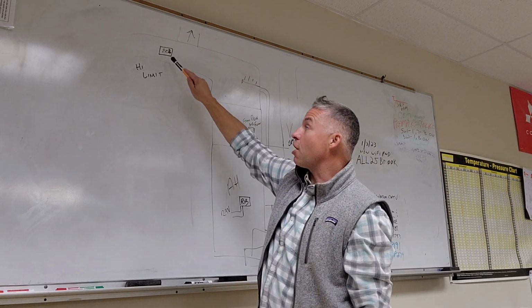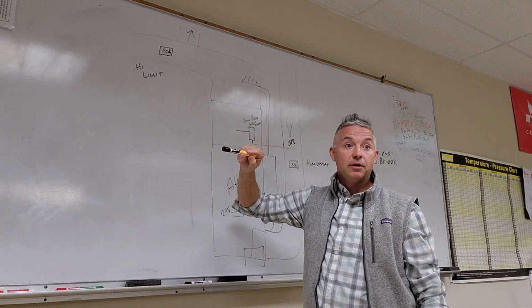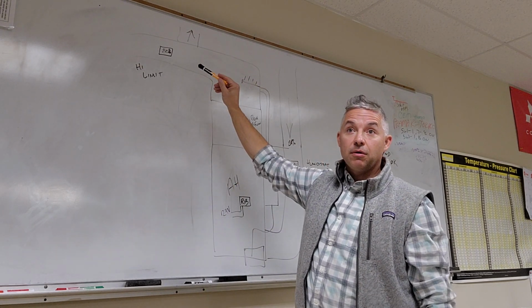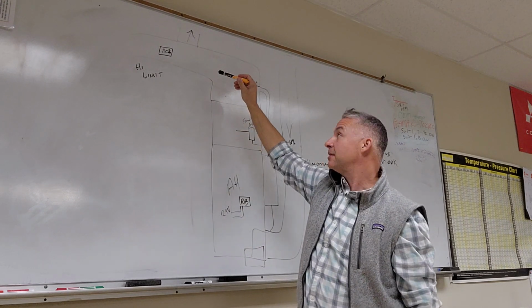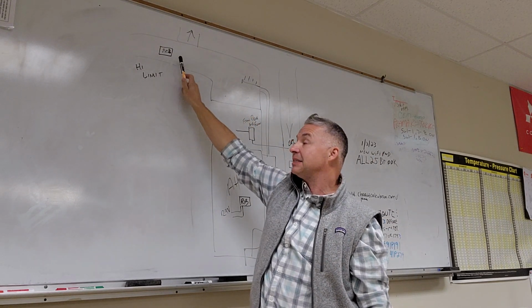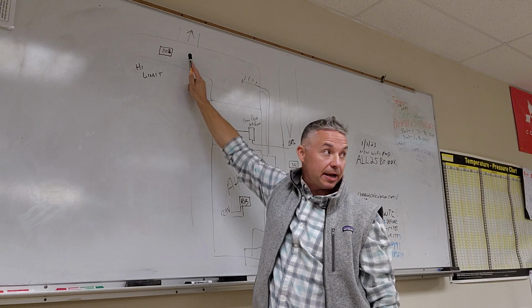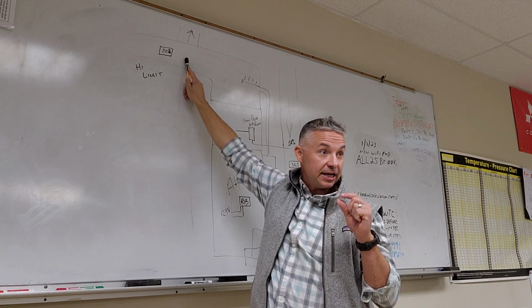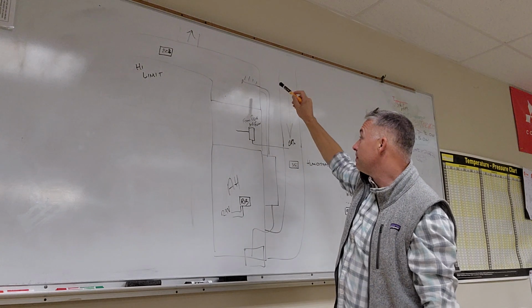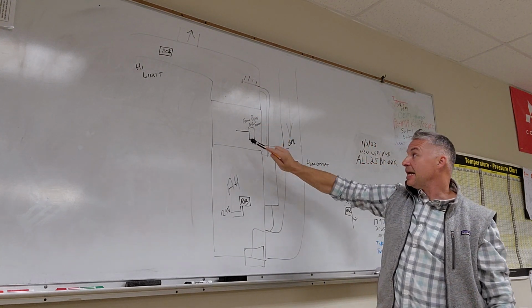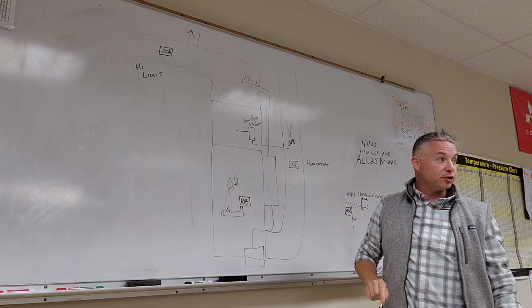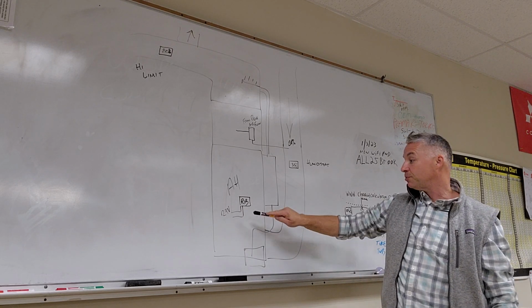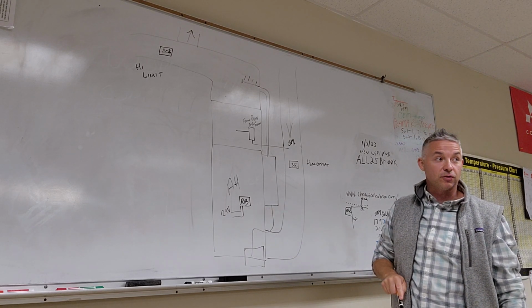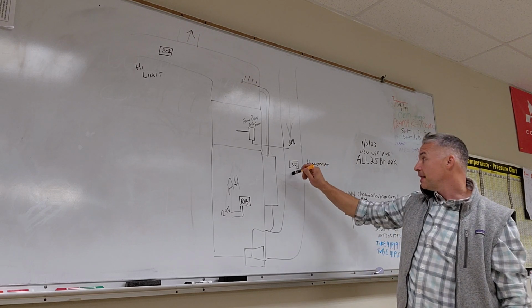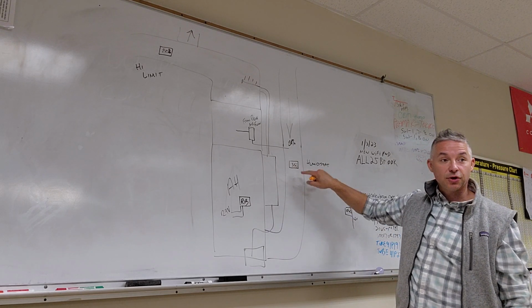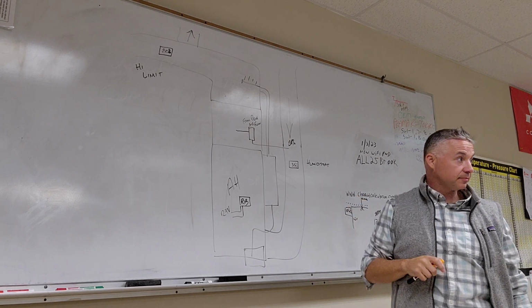And then we also have to go through our high limit and say, okay, that's also true. Now, the high limit being set at 80 is telling us that in this area we have less than 80% humidity, and that's what makes that switch close and stay closed. This one is telling us that, yes, I'm sensing airflow in the ductwork. I have a tube in this ductwork, and I'm sensing that I have fan speed. This is telling us that I do have a 24 volt signal for fan control, and that I am sensing that it's less than 35% humidity in the ductwork.